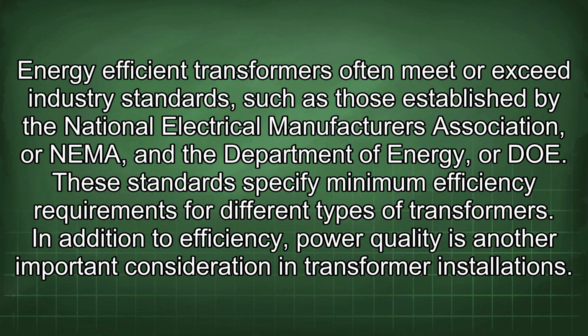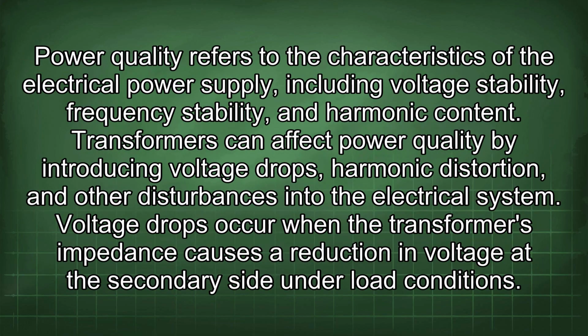Energy-efficient transformers often meet or exceed industry standards, such as those established by the National Electrical Manufacturers Association, or NEMA, and the Department of Energy, or DOE. These standards specify minimum efficiency requirements for different types of transformers. In addition to efficiency, power quality is another important consideration in transformer installations. Power quality refers to the characteristics of the electrical power supply, including voltage stability, frequency stability, and harmonic content.